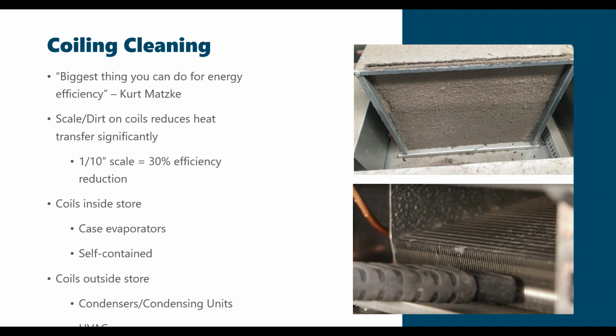And it's really true, and it's something that I think we all lose sight of in the utility industry when we're looking at widgets and the bells and whistles for efficiency, when a lot of times just cleaning condenser and evaporator coils can have a significant improvement on efficiency. Just as an example, 1/10 of an inch of scale is equivalent to a 30% efficiency reduction in terms of the heat transfer that you can get across that coil.